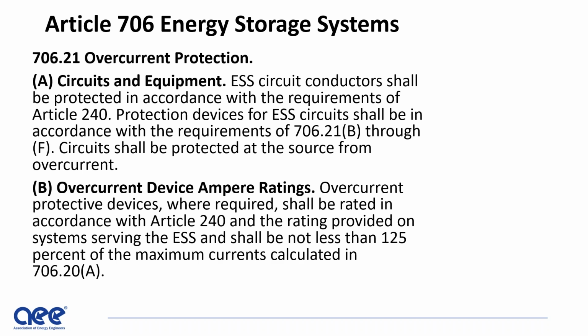For those of you that may not be familiar with the National Electric Code, it has 8 main chapters. Chapters 1 through 4 are the base requirements for electrical installations, and chapters 5 through 7 provide modifications to, or replace sections of, chapters 1 through 4. Chapter 8 is for telecommunications, and it stands on its own. In this case, for Article 706 in Chapter 7, instead of a replacement for Article 240, which is Overcurrent Protection, it sends you to that article and says you have to follow it, more as a reminder than a requirement, because Article 240 is part of the base requirements for electrical installations.